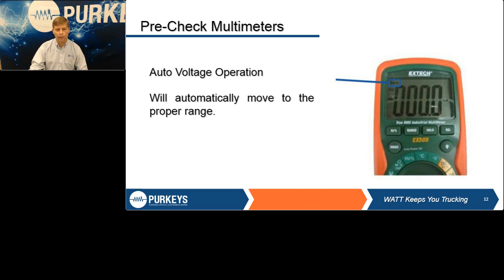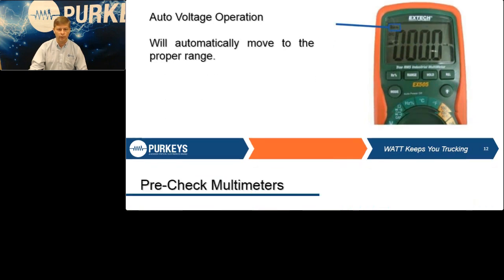One thing you always got to be very careful about, though, is say you're checking an outlet in your house. You put it on AC and you accidentally put it on a 20-volt scale. You go over there and stick the probes in the wall outlet. What's your meter going to read? Answer is, OL. Does that mean there's nothing there? No. You told the meter the highest you're going to see is 20 volts, and it's obviously going to be above that. So you got to be very careful. If you assume there's nothing there and start taking that outlet out, you'll find out real quick the hard way that no, there is still power there, just on the wrong setting for it.